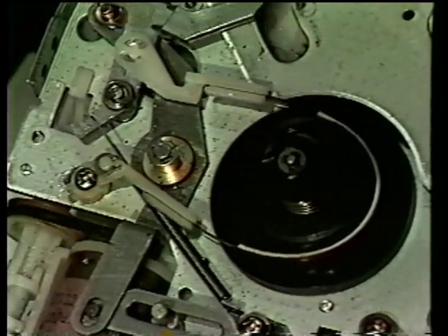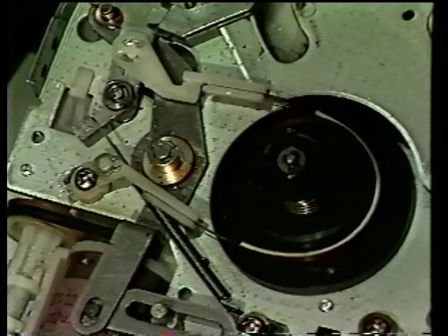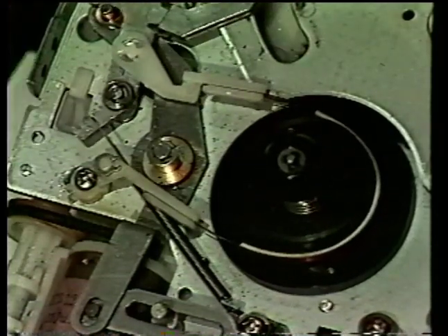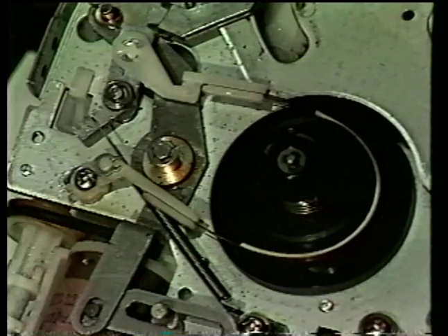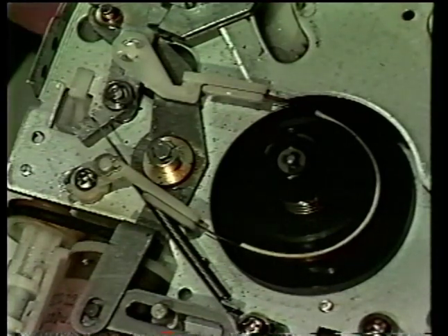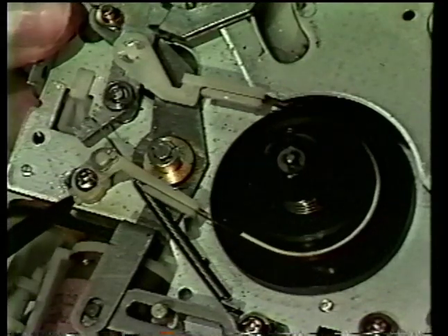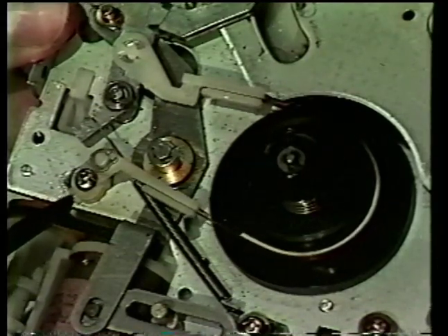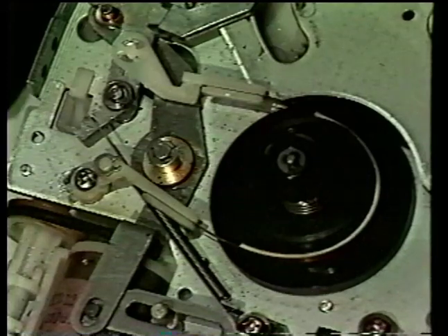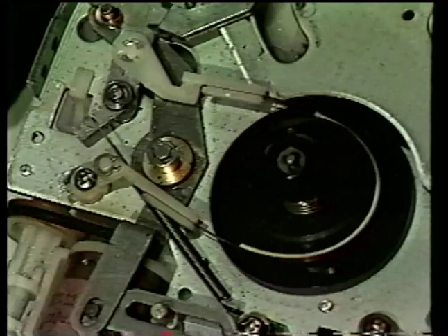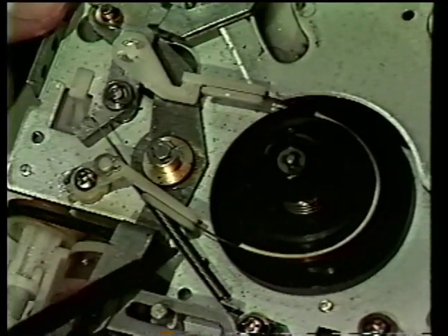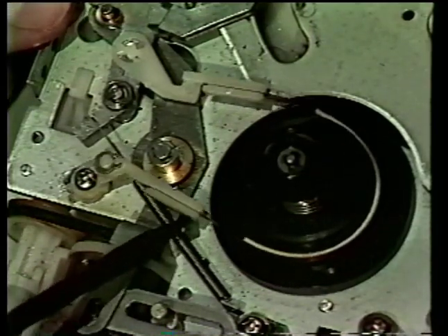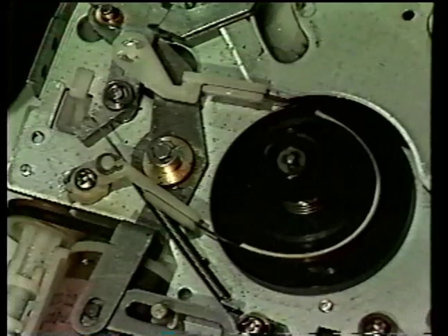This arm, the tension arm, is then connected to the other end of the band, so it does the same thing, being acted upon by the tape. You want to make sure that the tension stays in the 23 to 35 gram range by moving the fixed end to keep it within that range. If it turns out it's impossible to get the tension in that range, say that it goes from 20 to 50 grams, it may be necessary to change the position of this spring or actually replace the little brake band.